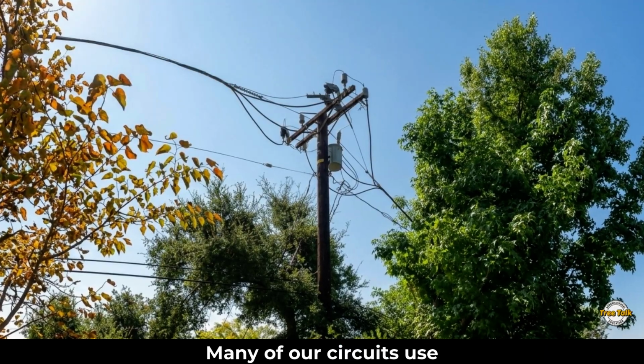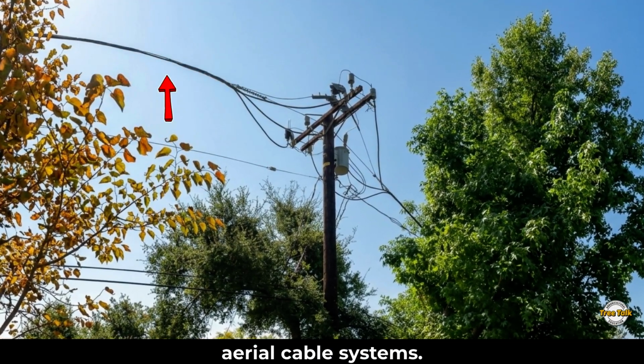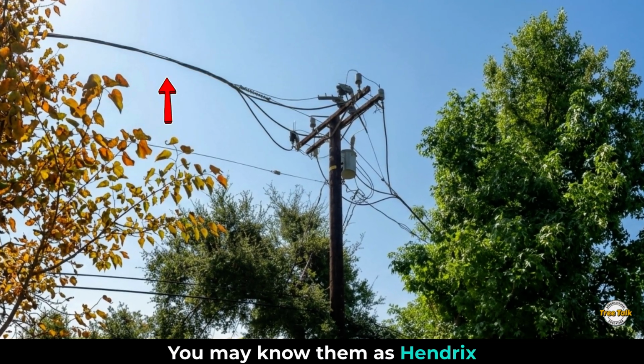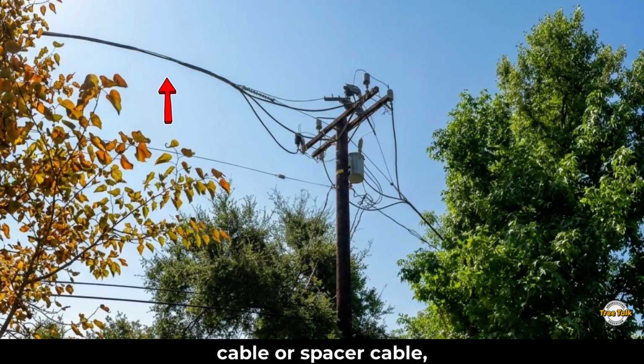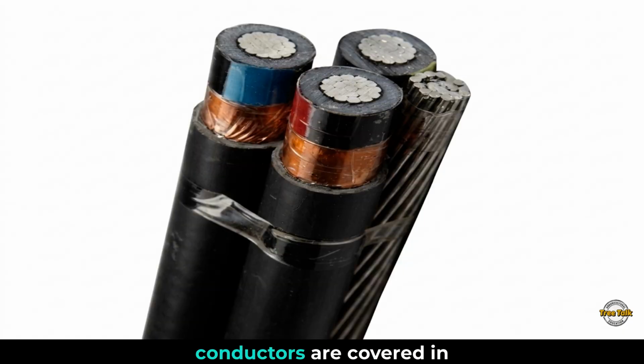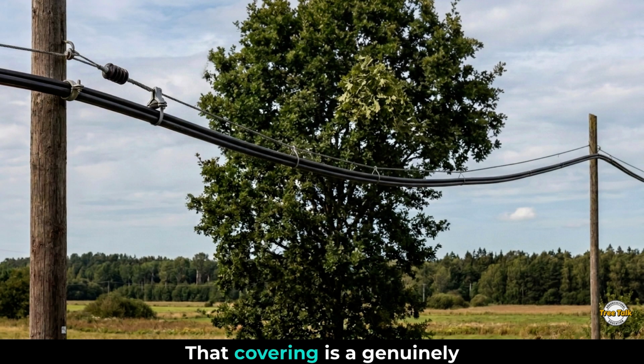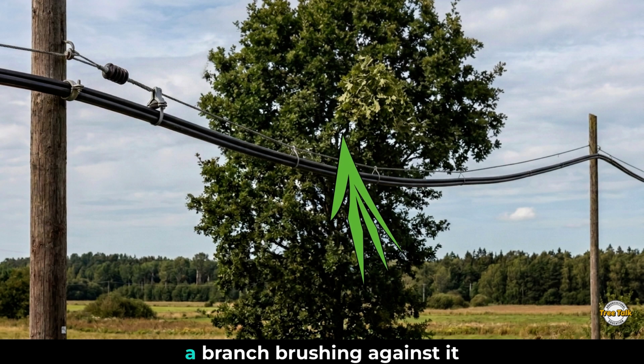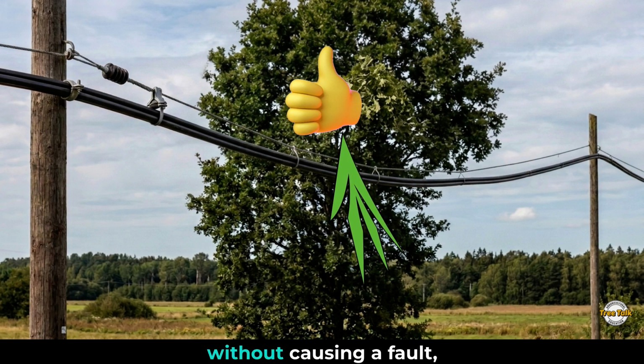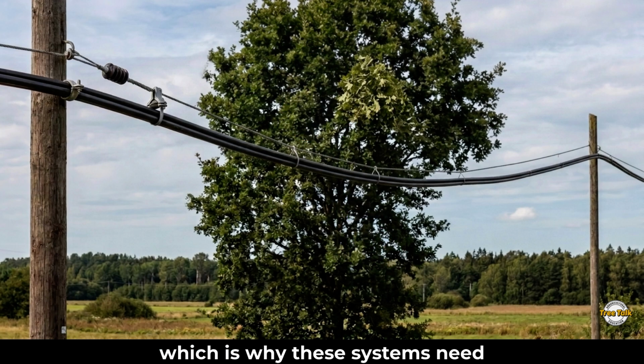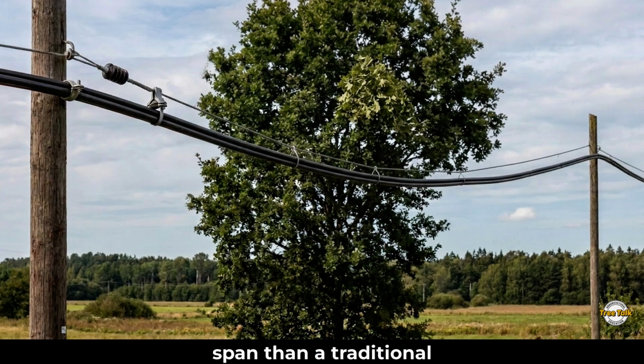Many of our circuits use aerial cable systems. You may know them as Hendrix cable or spacer cable, where the actual power conductors are covered in an insulating jacket. That covering is a genuinely good thing. It means the wire can tolerate a branch brushing against it without causing a fault, which is why these systems need less clearance along most of the span than a traditional bare wire does.